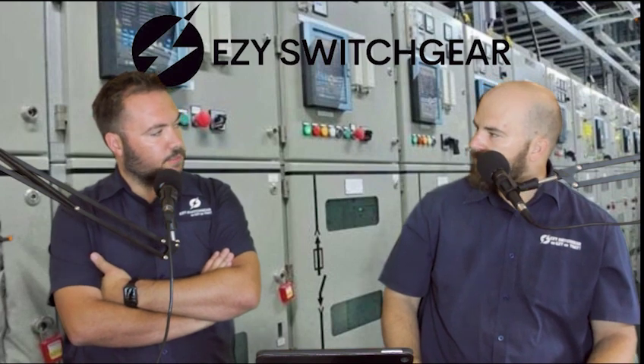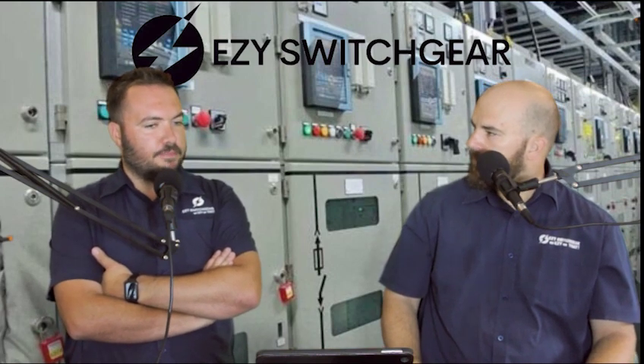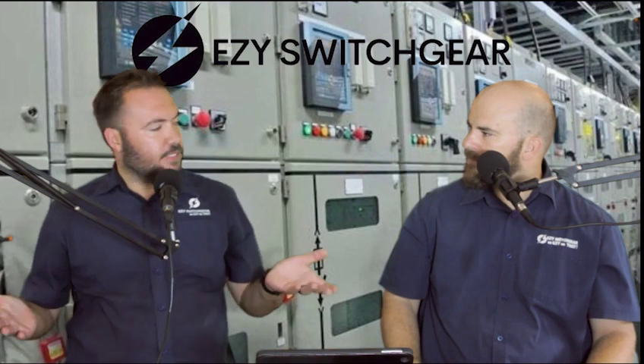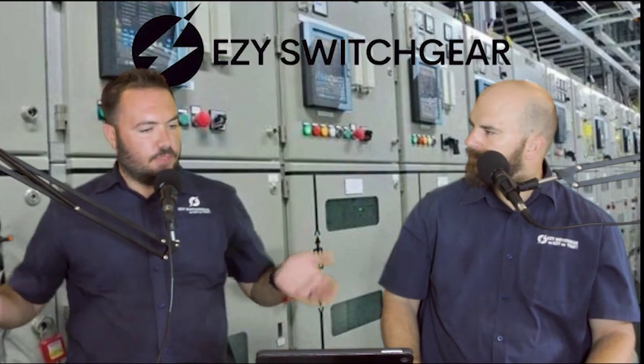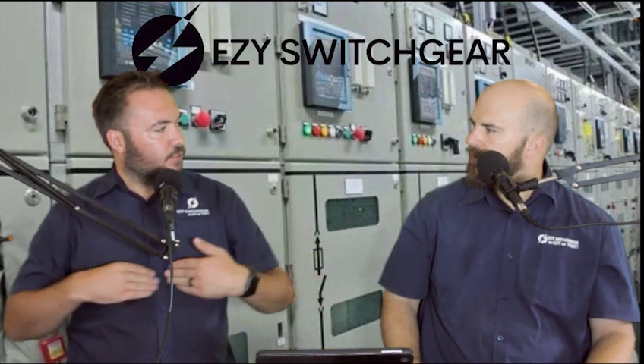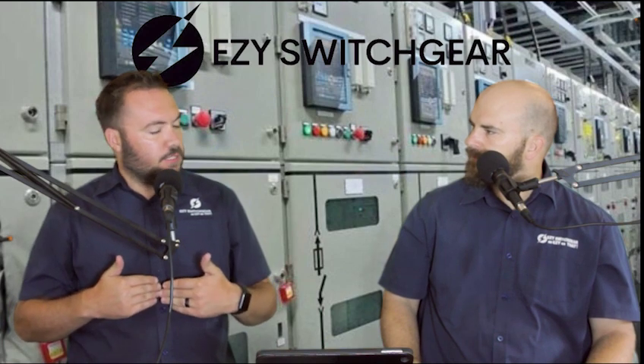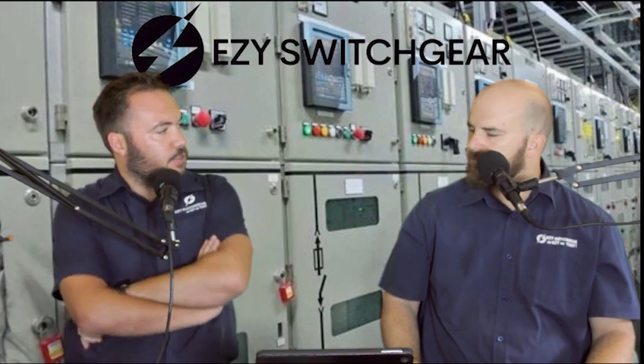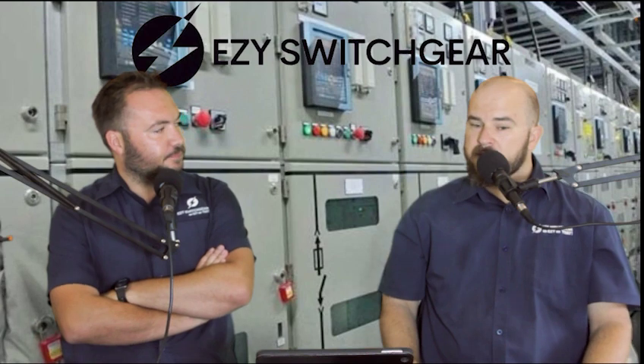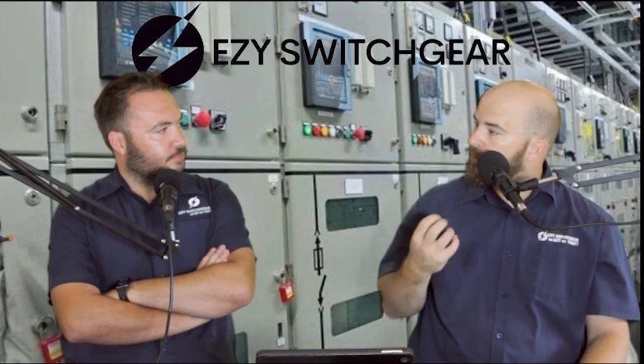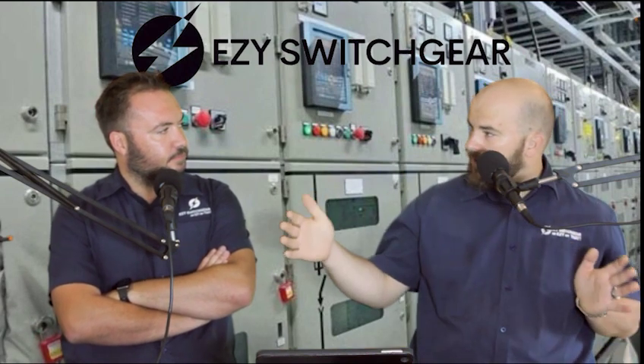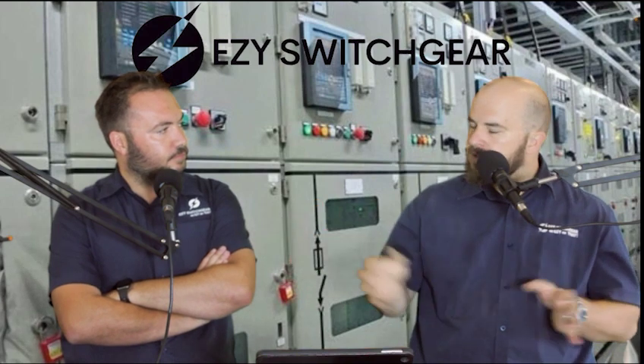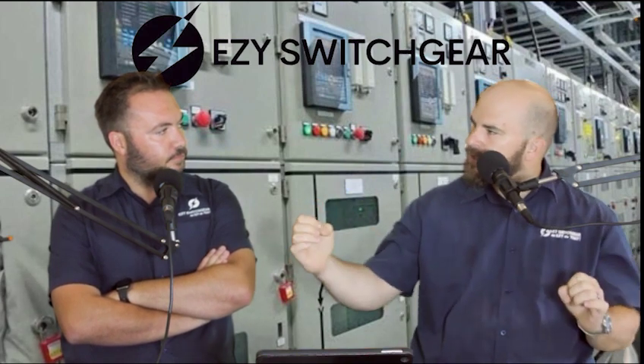Air insulated, yes. You just mentioned that if a cable is open in air, there is a big possibility of the voltage jumping between conductors. So how does air insulated switchgear work then? Yeah, air insulated switchgear has a few weaknesses. Number one, it's big in size. Okay, so why is it big in size? Because you need those insulating distances.